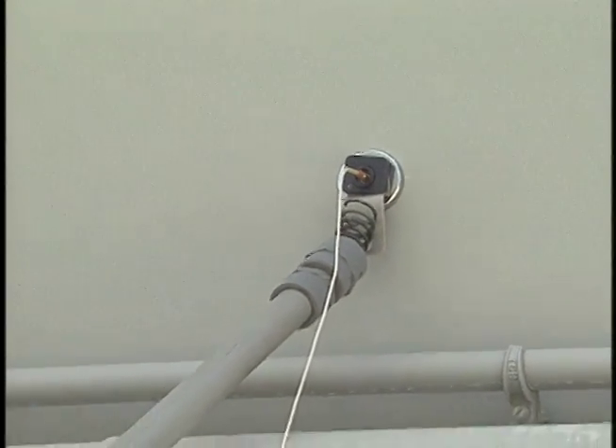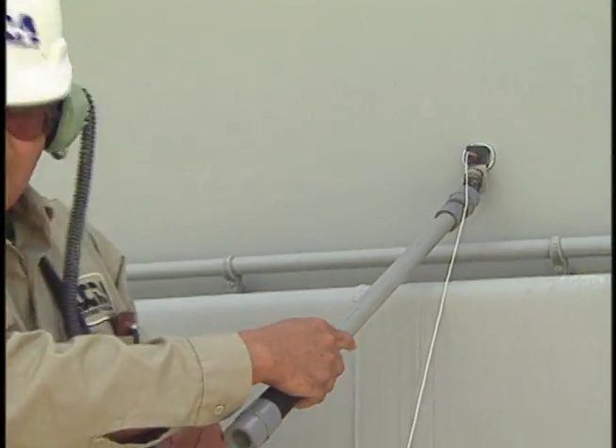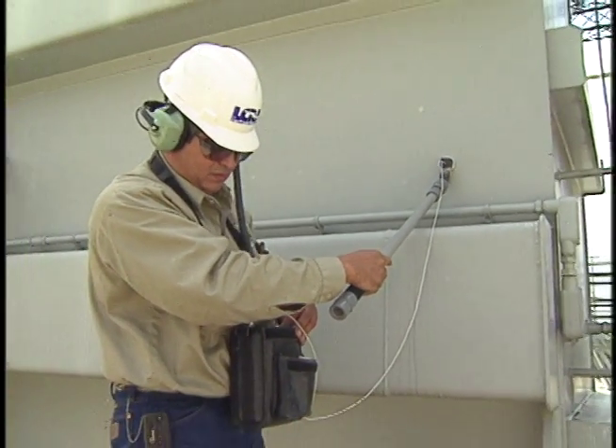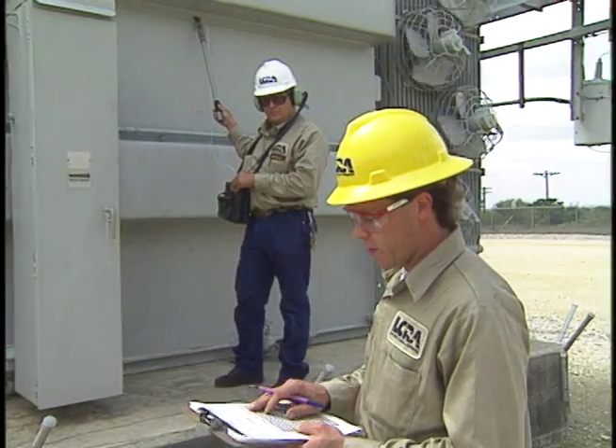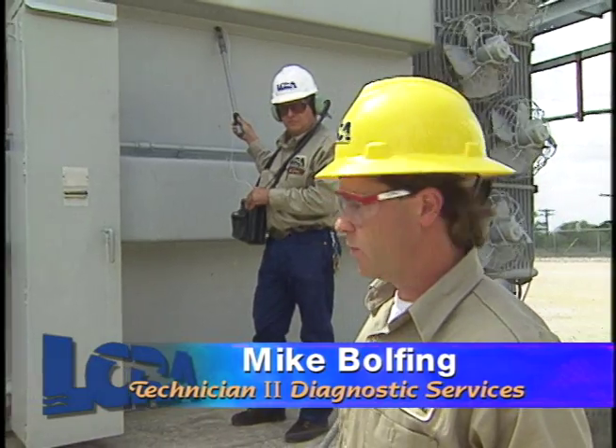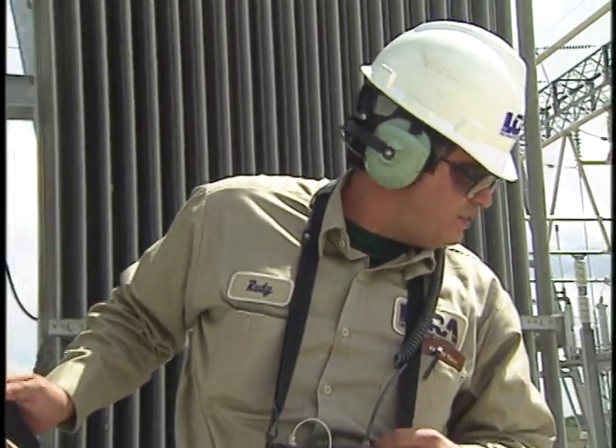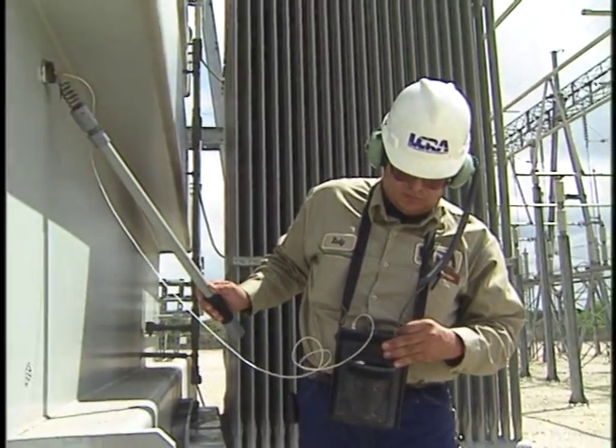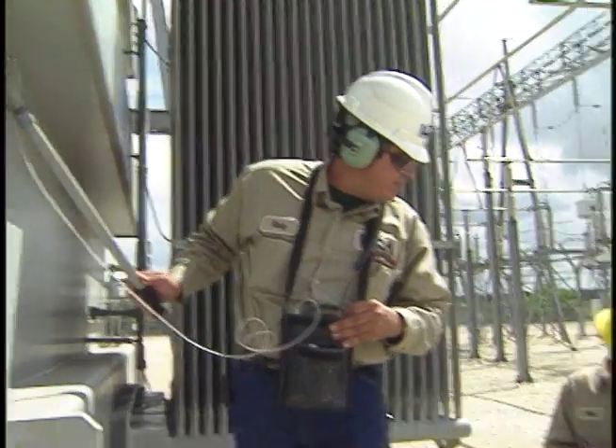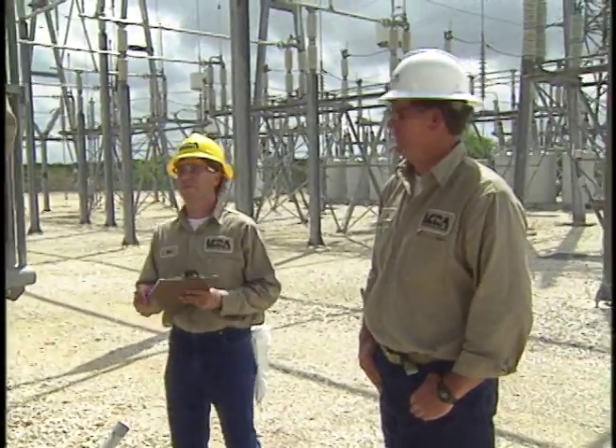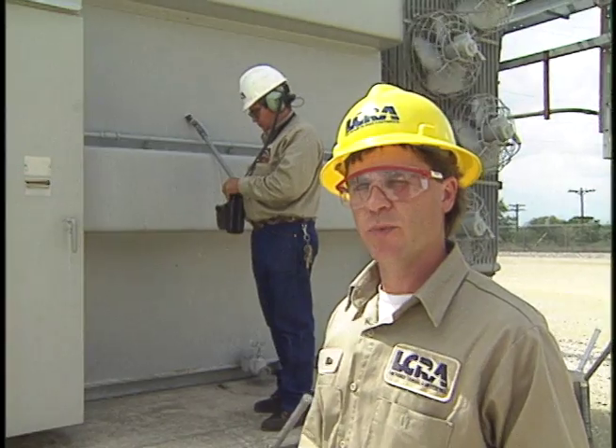This very sensitive microphone is used to listen inside the transformer for high and low frequency sounds that could indicate problems. You'll hear sizzling sounds, which is arcing inside the transformer. If we hear this, we'll pull oil samples and combustible gas samples to see if we have high gas concentrations in the transformer. In the lower frequency range, it's a vibration, and it lets you know if there are loose mechanical parts vibrating inside the transformer, which could cause problems.